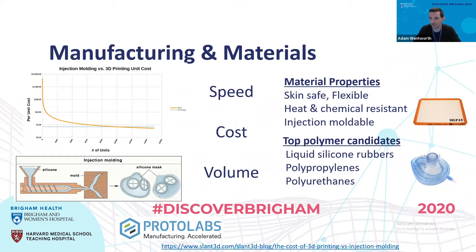There are three major factors to consider in prototyping: speed, cost, and volume. We can produce some prototypes in-house that are very fast, but at a volume of only one or two, and relatively high in cost — those are not scalable. Those, for example, could be 3D printed. Looking at the graph, injection molding versus 3D printing cost curve: injection molding is initially very expensive, but at units of 10,000 or more, which is the objective, your cost becomes lower than 3D printing. You can see a schematic of how injection molding works — injecting a viscous material into a mold cavity, it cures to a solidified state, and then you can pop out the product.